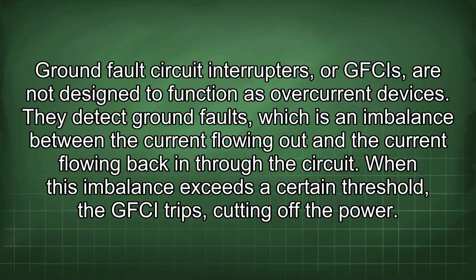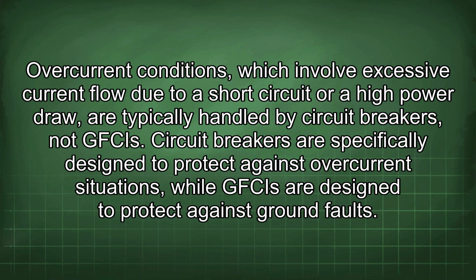Ground fault circuit interrupters, or GFCIs, are not designed to function as overcurrent devices. They detect ground faults, which is an imbalance between the current flowing out and the current flowing back in through the circuit. When this imbalance exceeds a certain threshold, the GFCI trips, cutting off the power. Overcurrent conditions, which involve excessive current flow due to a short circuit or a high power draw, are typically handled by circuit breakers, not GFCIs. Circuit breakers are specifically designed to protect against overcurrent situations, while GFCIs are designed to protect against ground faults.